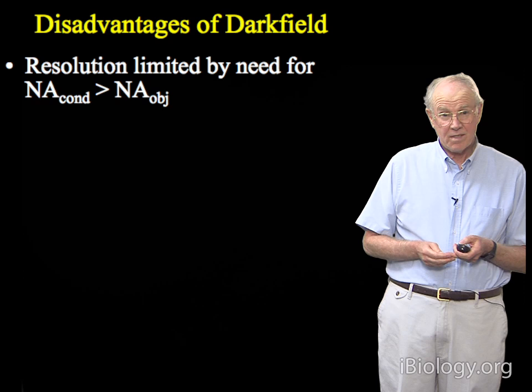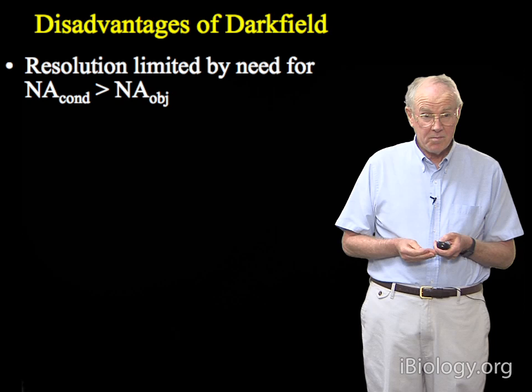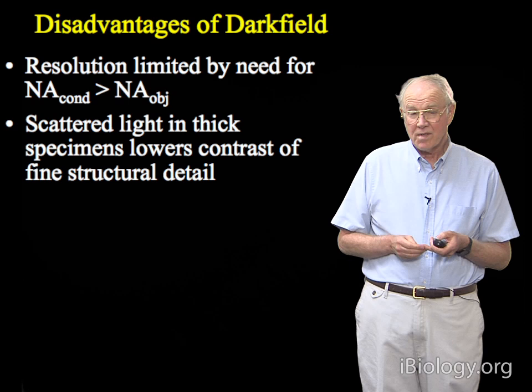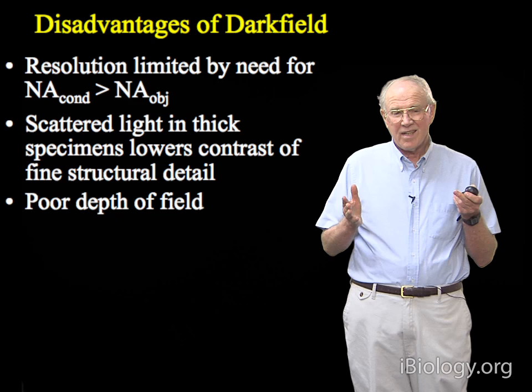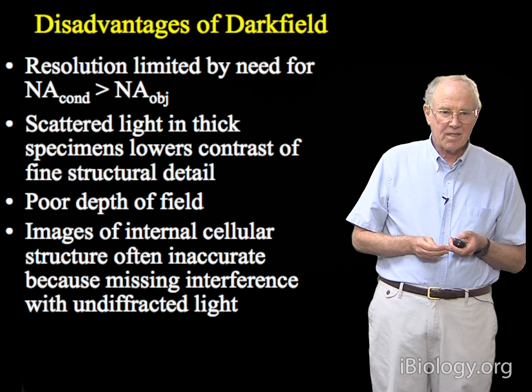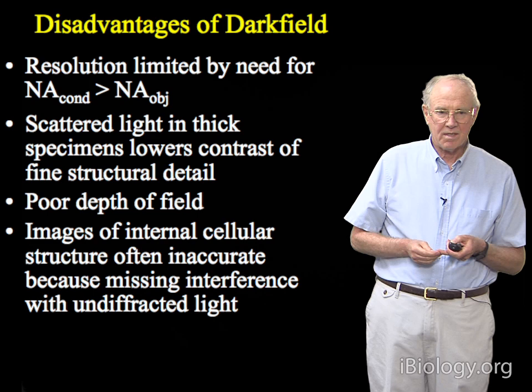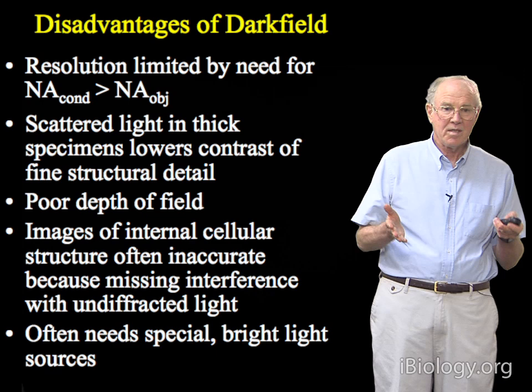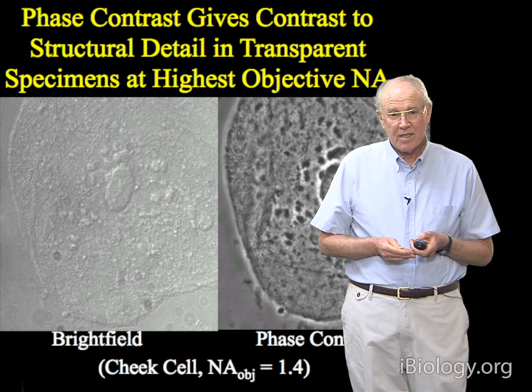Dark field has a lot of disadvantages though. Because the NA of the condenser is greater than the NA of the objective, you get a limit in the actual resolution you can achieve. There's also a lot of scattered light in dark field imaging for any thickness in specimens, which obscures fine structural detail. It has poor depth of field because scattered light is carried up the optical axis of the microscope, and images of internal cellular structures are often inaccurate and confusing because you're missing the fidelity that you get by having interference with the undiffracted light. You often need very bright light sources to make a good image in dark field.